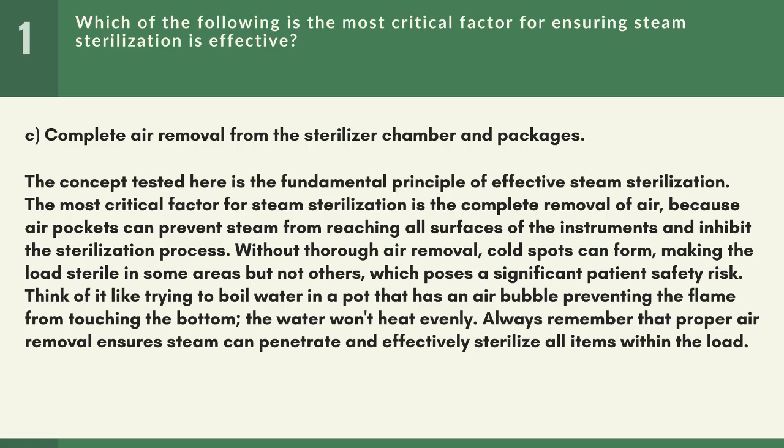Without thorough air removal, cold spots can form, making the load sterile in some areas but not others, which poses a significant patient safety risk. Think of it like trying to boil water in a pot that has an air bubble preventing the flame from touching the bottom. The water won't heat evenly. Always remember that proper air removal ensures steam can penetrate and effectively sterilize all items within the load.